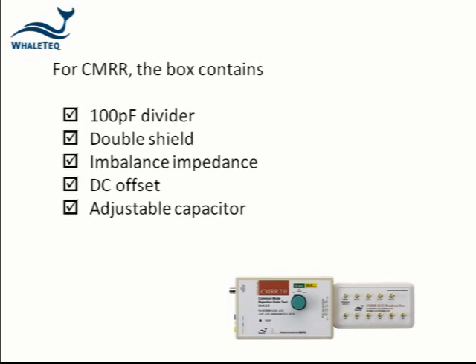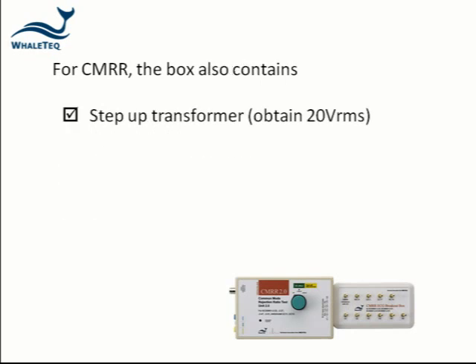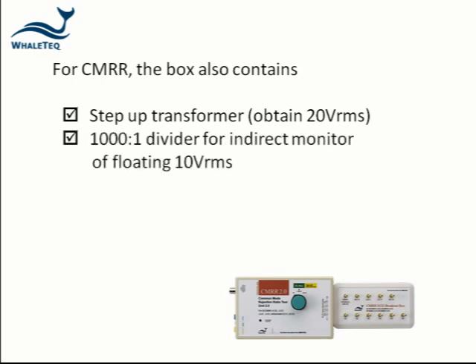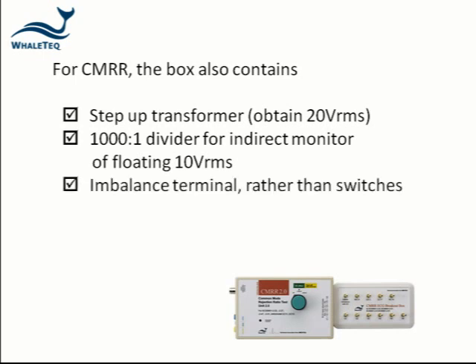It also contains a step-up transformer to obtain 20 volts RMS, a 1000-to-1 divider to monitor the floating 10 volts RMS, and an imbalance terminal instead of the switches in the standard. More detail on the CMRR test method and theory behind the test is provided in a separate video.